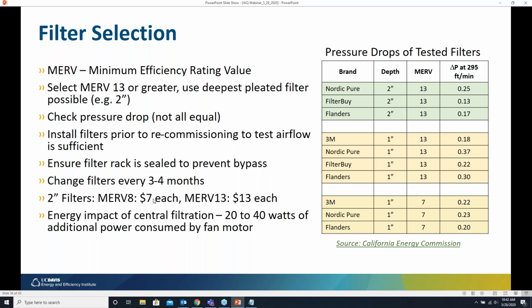And I also want to point out that the energy impacts of adding MERV 13 filtration in central HVAC systems are pretty small. The pressure drop caused by the filters increases your fan motor power by 20 to 40 watts continuously when the fan is running. That's about the power consumed by a computer monitor.